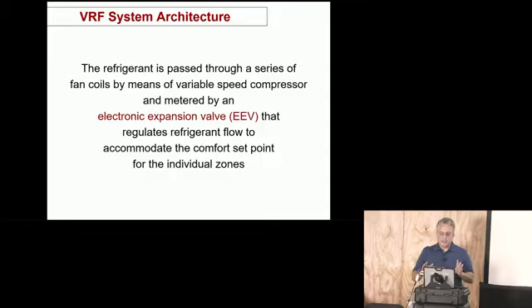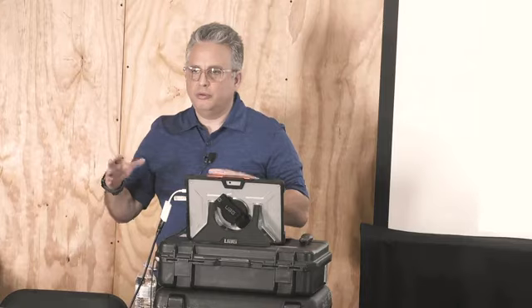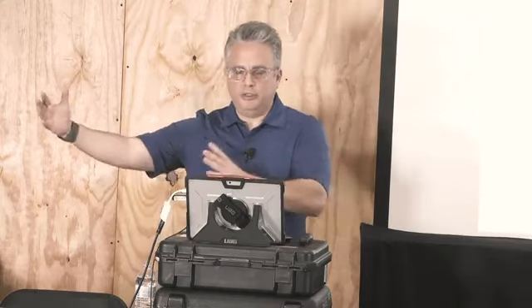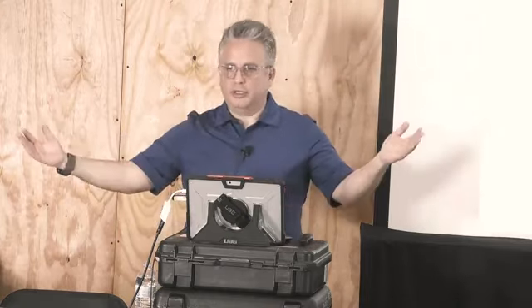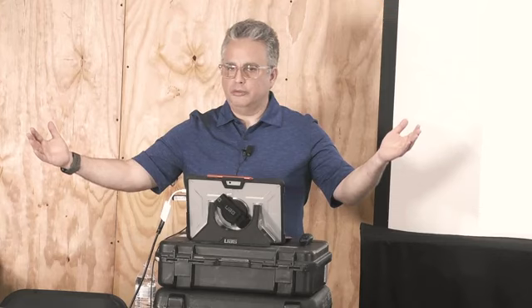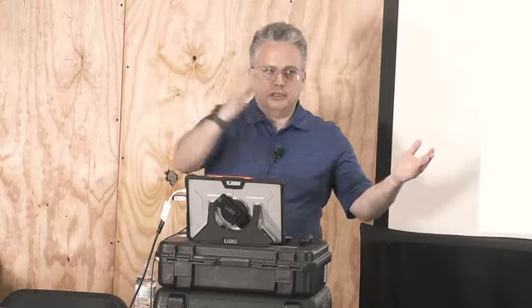The refrigerant is passed through a series of fan coils by means of a variable speed compressor and metered by an electronic expansion valve that regulates refrigerant flow to accommodate the comfort set point for individual zones. So basically, when you look at a multi-zone or a VRF system, each indoor unit is a single zone to the outdoor unit, right? Each indoor unit is its own zone.